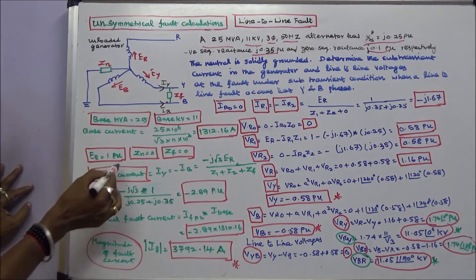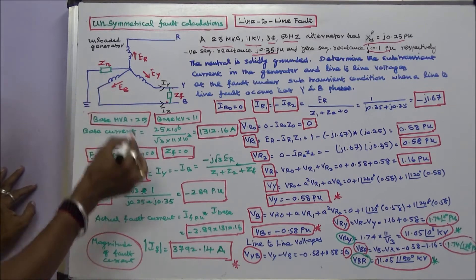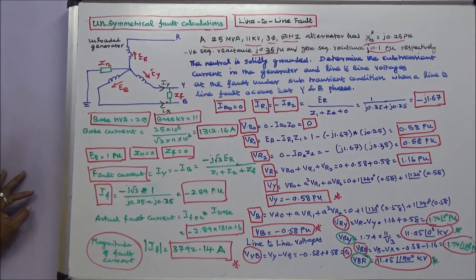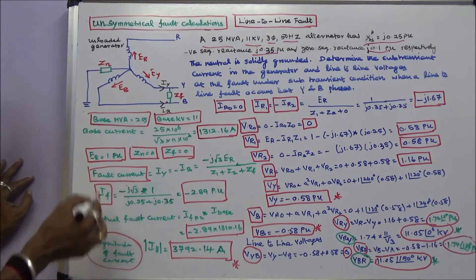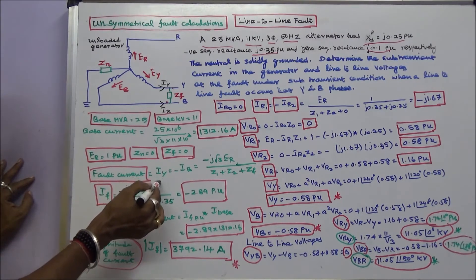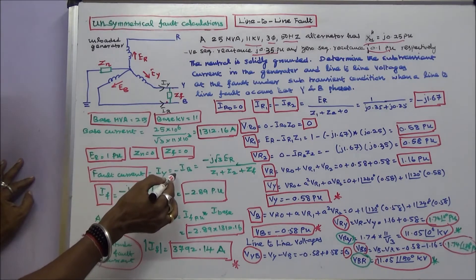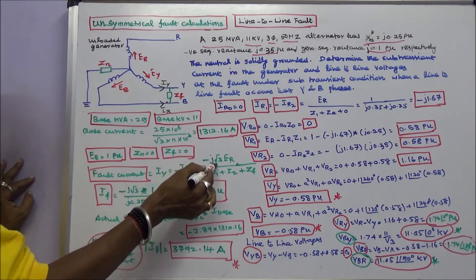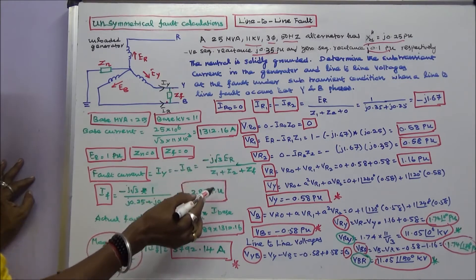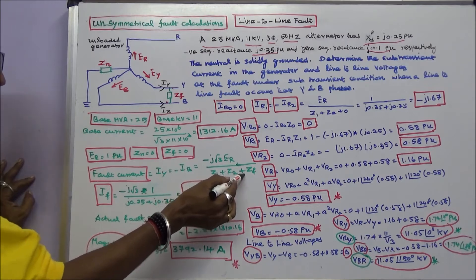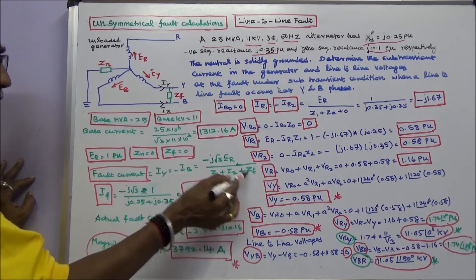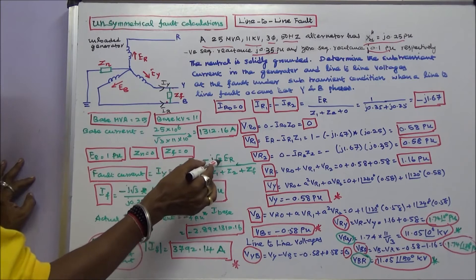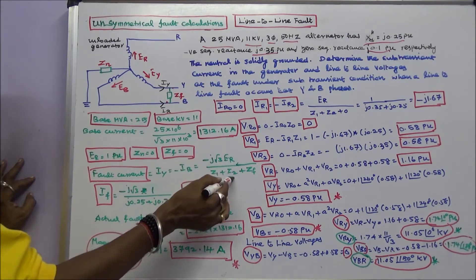Here ER is equal to 1 per unit, ZN is equal to 0, ZF is equal to 0. We know that fault current IY equals minus IB, equal to minus j into root 3 into ER divided by Z1 plus Z2 plus ZF. Here ZF is 0, therefore it becomes minus j into root 3 into ER divided by Z1 plus Z2.